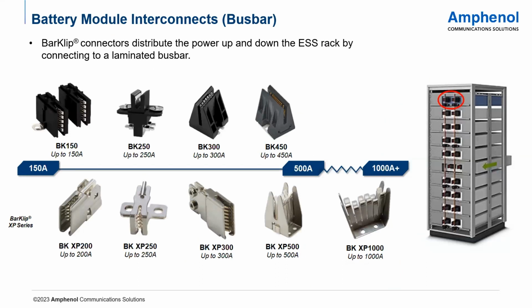Another somewhat common variation of energy storage system power distribution is through bus bars. As you can see here, you would slide the battery modules into the rack, and once fully slid in, both the BarKlip or bus bar connectors would mate to the laminated bus bars and distribute power up and down the system.